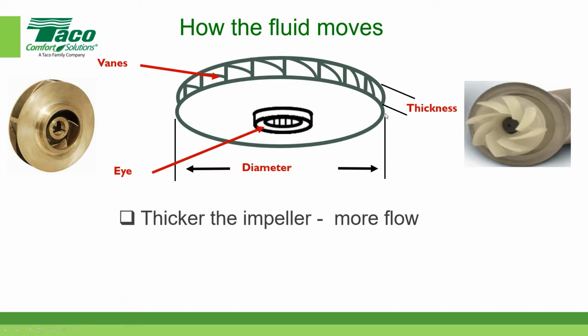The thicker the impeller, the more flow. Think of this thickness here as the ability to sling or slap more water than a thinner one. Okay, thin ones can't hold as much water. Thicker ones can hold more water. Therefore, the end result is generally more flow. Okay, we're showing you a couple different ones. Here's a closed impeller that shows those vanes. Here's an open impeller, like an older standard efficiency impeller. Notice it's open. It's not capped on the top. This would still be down inside the casing or the volute, but this would be considered the eye, and it's spinning in this direction. This one is spinning in this direction.